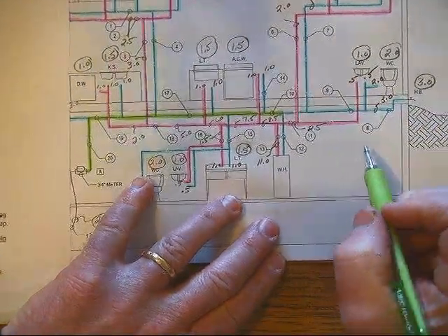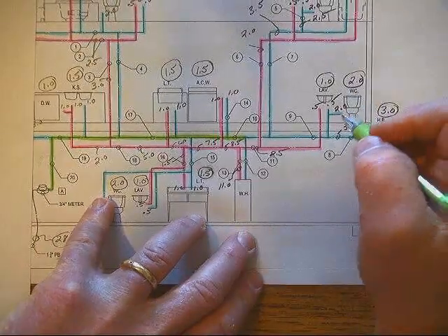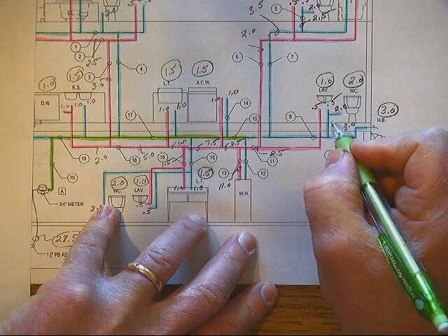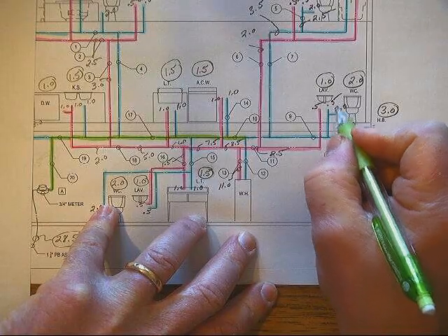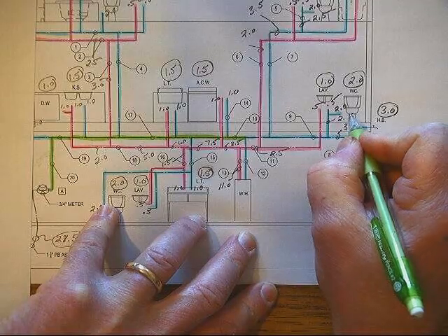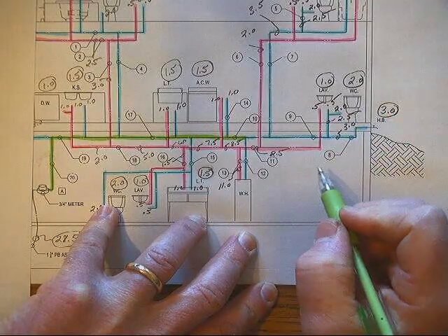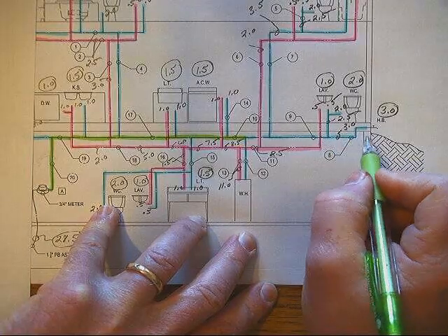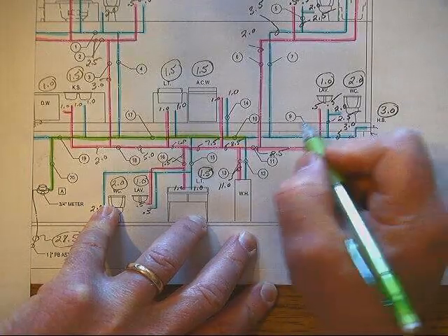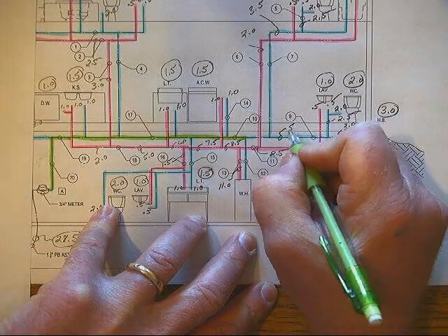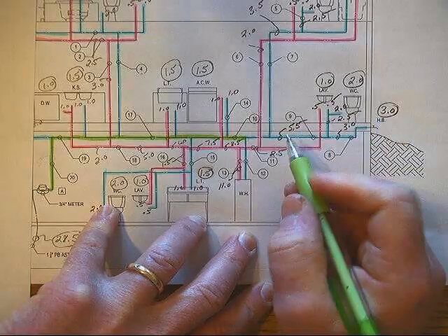We'll work our way down to the lower level, and here we had another piece of water distribution piping that had a lav and a water closet on it. This will be 2.5 on this piece of pipe. That riser there ties in with the hose bib, and this pipe number 9 here would then have 5.5 on it.